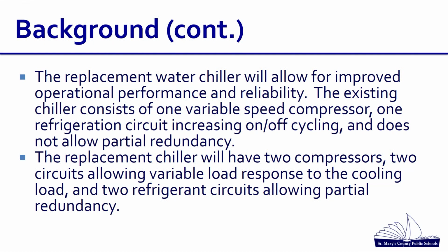The replacement chiller we spec'd will have two compressors and two circuits, allowing variable load response to the cooling load, and the two refrigeration circuits will allow partial redundancy. If a mechanical or electronic apparatus in one of the circuits fails, you still have the other circuit to run, so a third to 50% cooling will still be available.